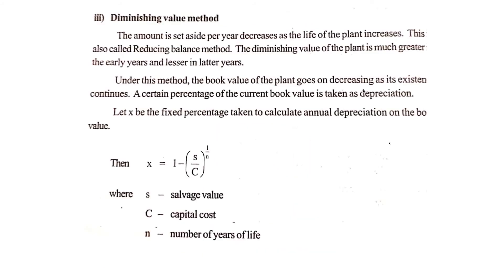The third method is the diminishing value method, also called the reducing balance method. In this method, the amount set aside per year decreases as the life of the plant increases. A fixed percentage is used to calculate the annual depreciation. The formula is: x = 1 − (S / C)^(1/n), where S is the salvage value, C is the capital cost, and n is the number of years. As the plant's existence continues, the plant value decreases, and this percentage captures that reducing depreciation.